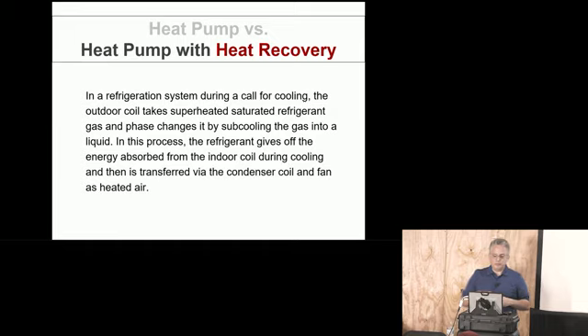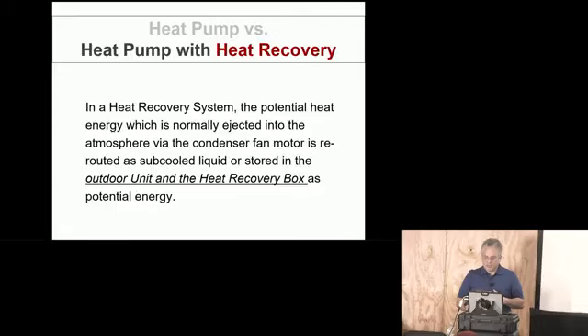So in a refrigeration system, during a call for cooling, the outdoor coil takes superheated saturated refrigerant gas and phase changes it to subcooled liquid, subcooling the gas into a liquid. In this process, the refrigerant gives off energy absorbed from the indoor coil during cooling, and then transfers that to the condenser coil as heated air, right? We all understand that, or we're beginning to understand that? Well, with the heat recovery system, that potential heat energy, which is normally ejected into the atmosphere, is rerouted as subcooled liquid and can either be stored or used by the heat recovery box.